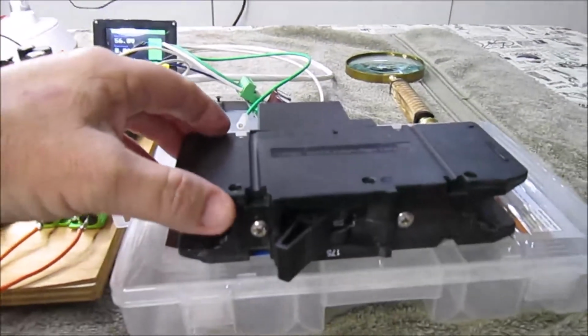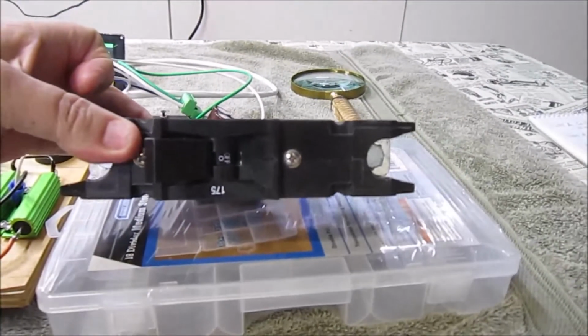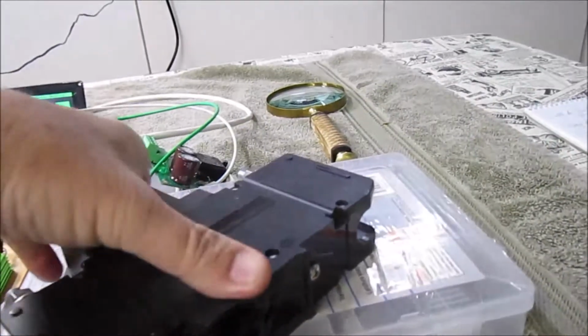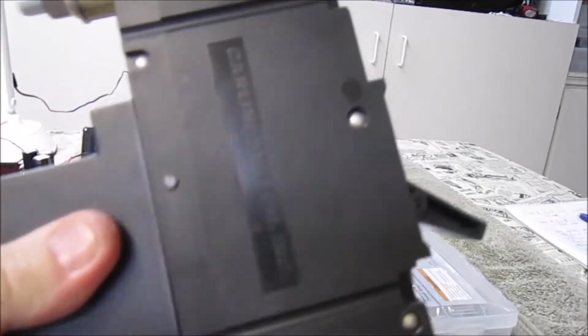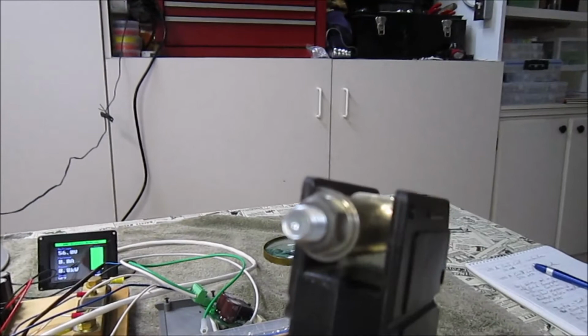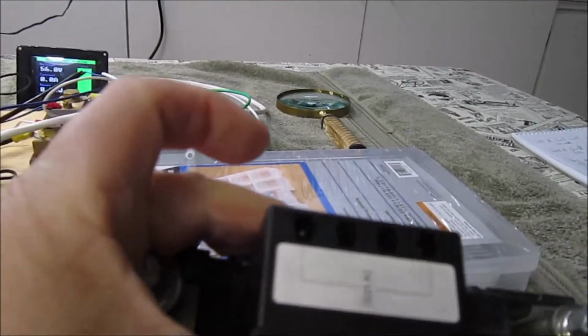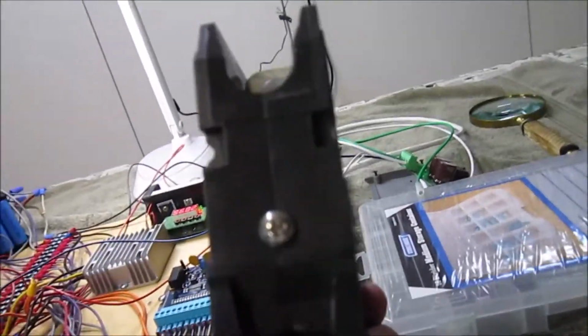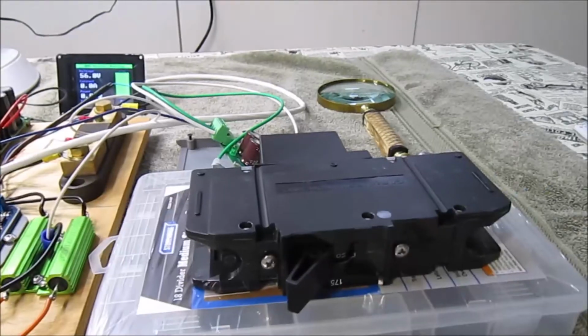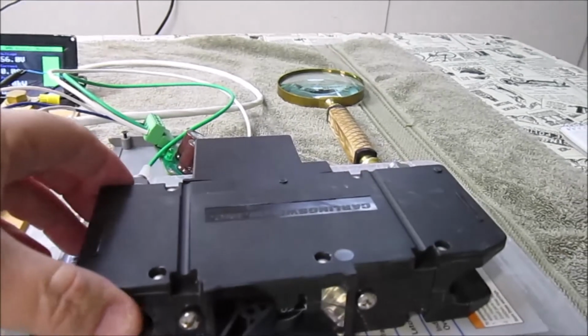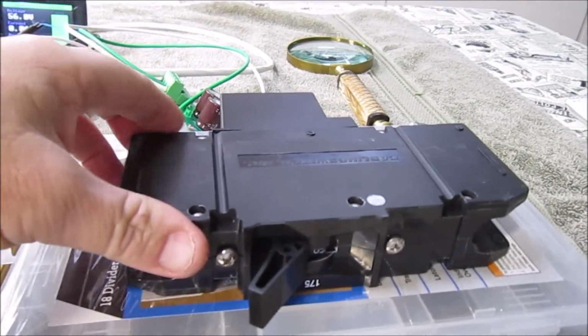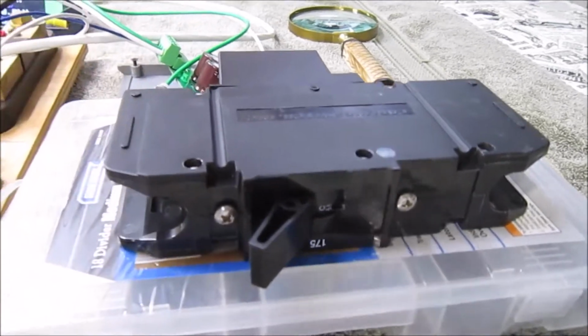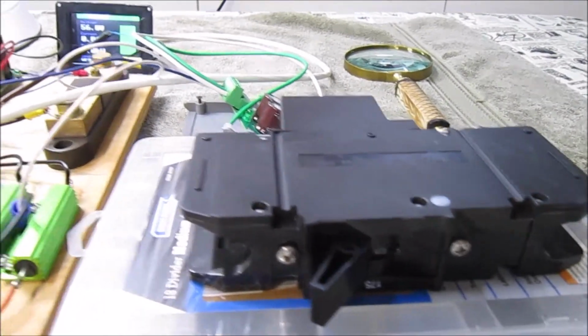I've got this Midnight Solar 175 amp remote trip breaker. It's based on Carling Technologies Type F breaker. It's pretty beefy. A 3/8 post, 24 volt trip coil, non-polarized, and it's a panel mount with, I think they're 10-32 screws.